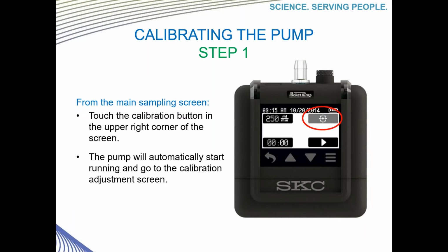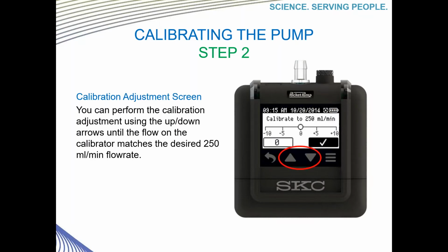In this scenario, the pump would already be at the main sampling screen after we accepted the flow rate earlier. So you would touch the calibration button in the upper right-hand corner. The pump will automatically start running and change to the calibration adjustment screen. At this point, you can use the up and down arrows to speed up and slow down the pump's motor until the flow rate indicated on the calibrator reaches the desired 250 milliliters per minute. It is important that you note that you're not changing the displayed flow rate on the pump, only the pump speed, in an effort to truly calibrate the pump to match your calibrator or flow meter.